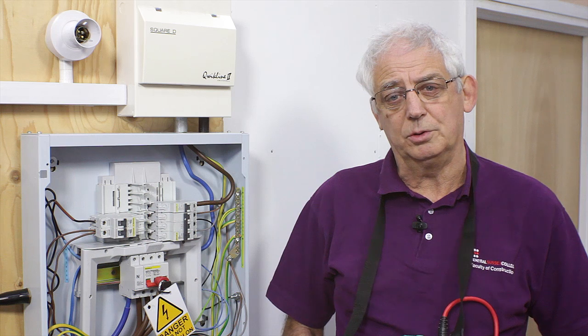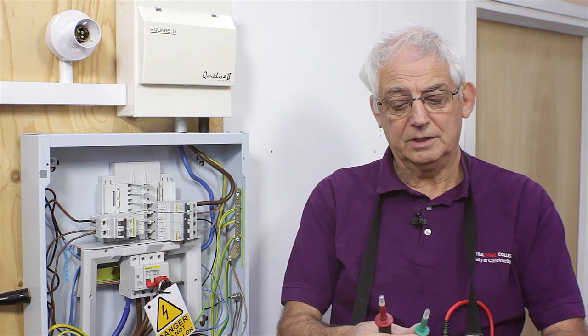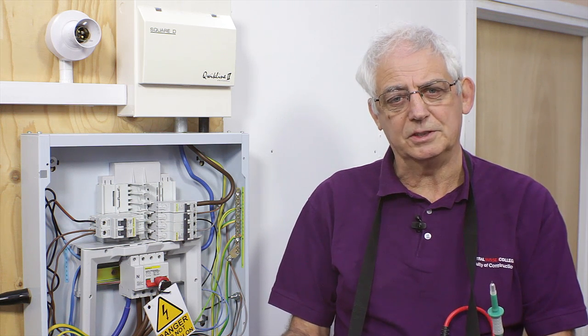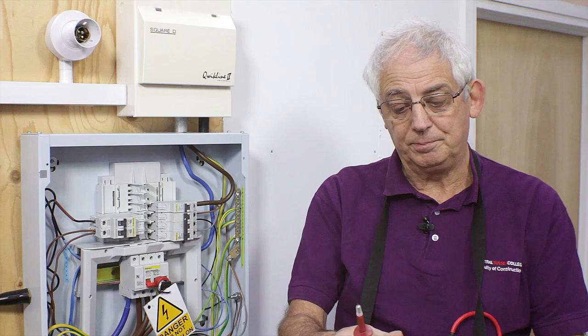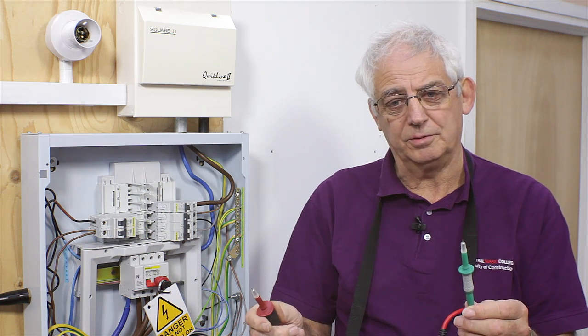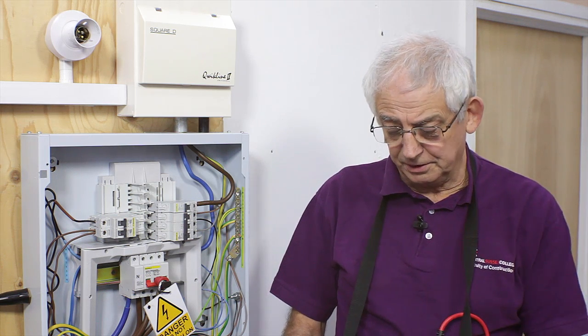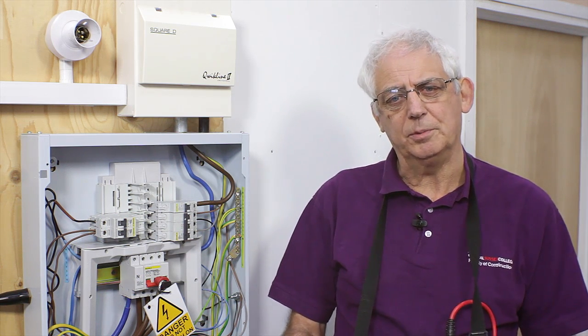One of the first things I need to do when I'm carrying out an insulation resistance test is to make sure, of course, the probes are in good condition. The ends of the probes are protected to comply with GS38 because this is really a 500 volt test. GS38 applies to any equipment over 50 volts. I also need to make sure that the instrument is working properly.